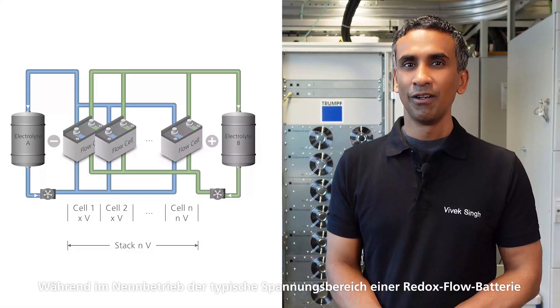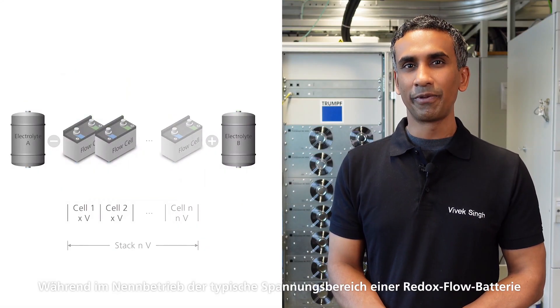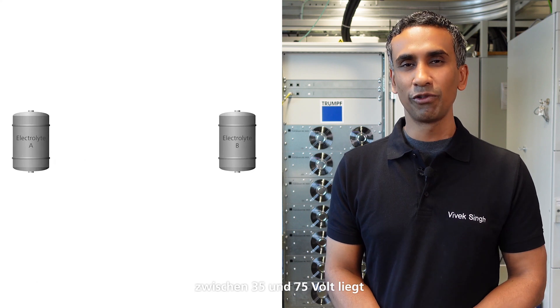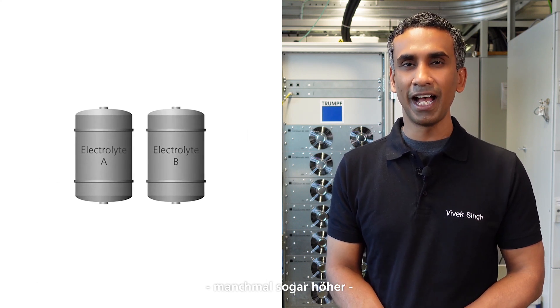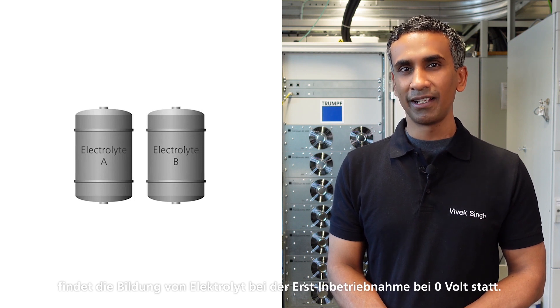Another tricky part that flow battery manufacturers face is the electrolyte formation prior to normal operation of a flow battery cell. While a normal operational voltage range of a flow battery could be anywhere between 35 to 75 volts — sometimes even higher — the electrolyte formation happens at zero volts.